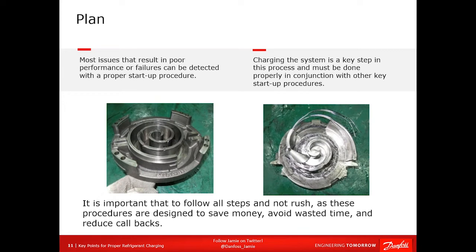On simple systems like piston systems in AC — a simple orifice, just a hole — the amount of flow through that orifice is determined by the pressure differential. As you add refrigerant, the pressure differential increases between the high and low side, causing more refrigerant to flow through the piston. Charging the correct amount is just as critical for fixed orifice systems as for TXV systems — even more so — because if you overcharge a piston system, you greatly increase the chance of liquid return to the compressor. It doesn't matter if it's a scroll or reciprocating: if you get liquid coming back regularly, it will seize and you will destroy it.